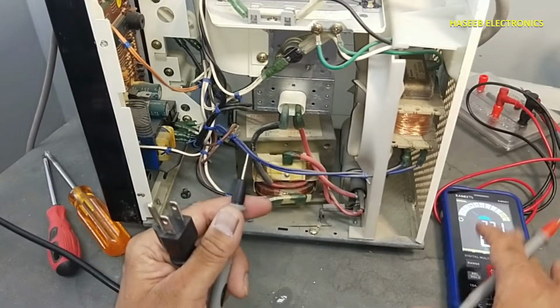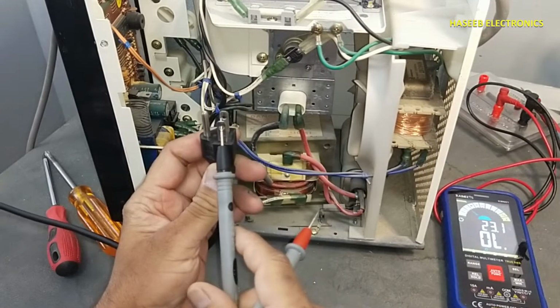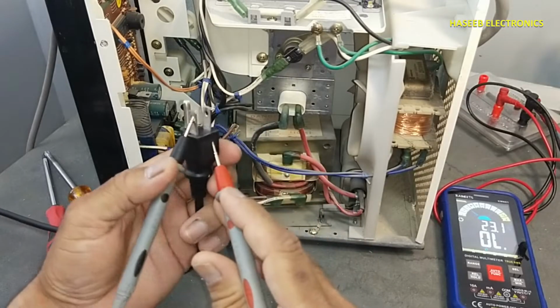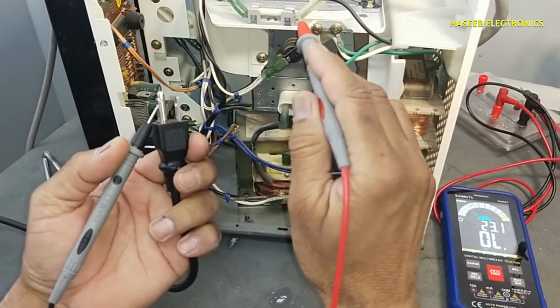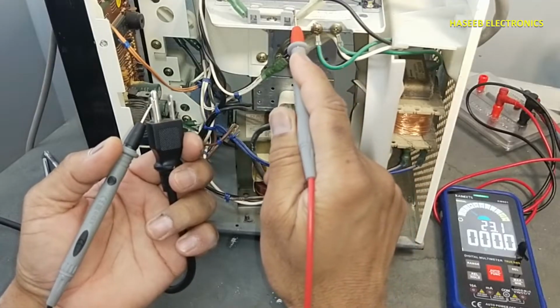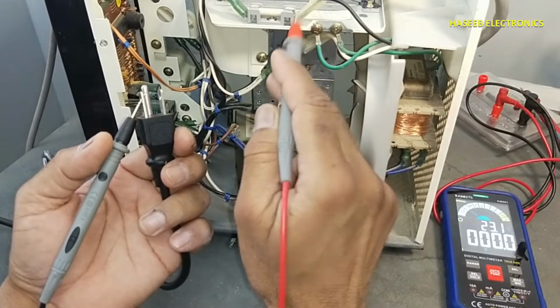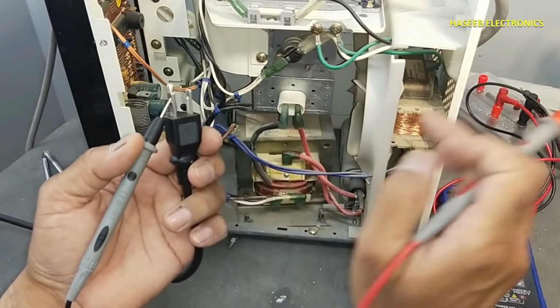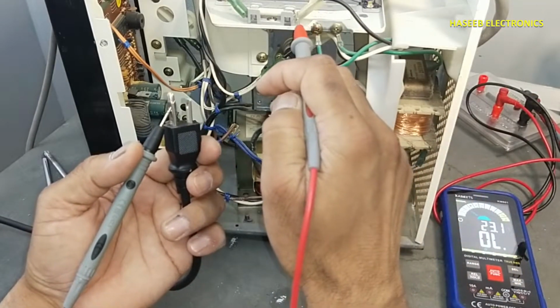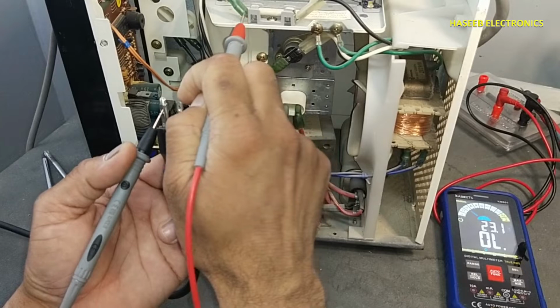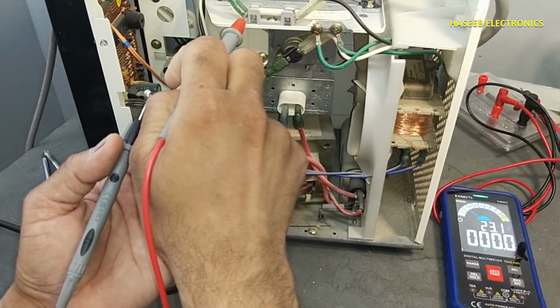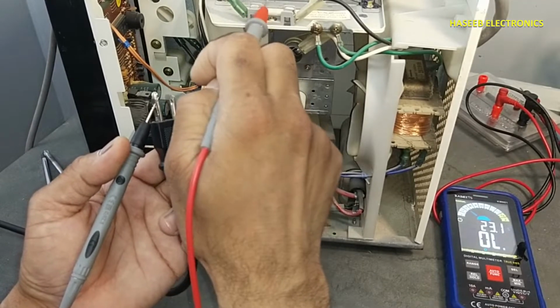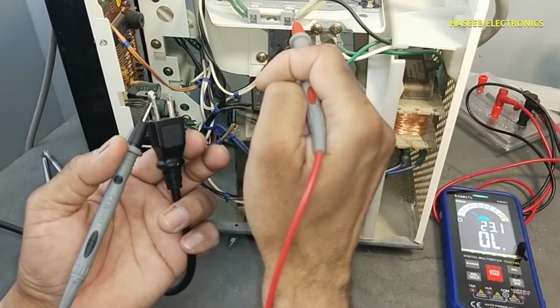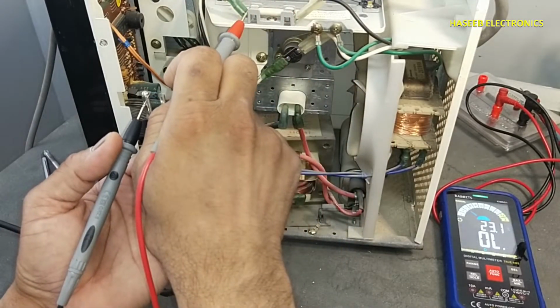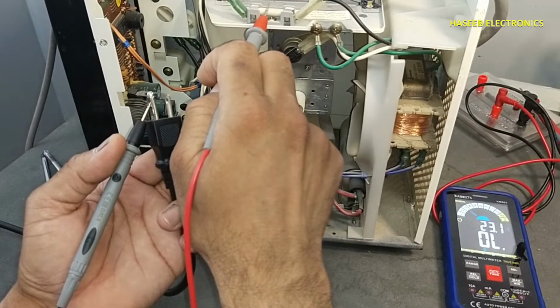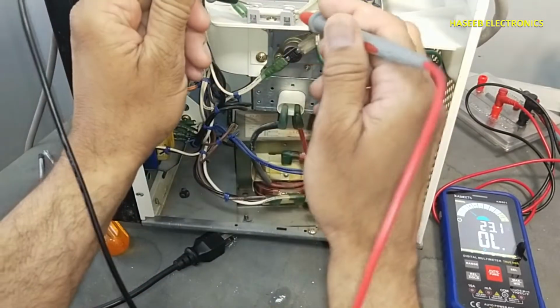Set the multimeter to continuity. Connect one lead to one input terminal, and connect the other to one end of the fuse. If it is giving continuity here, that means from this point to this point the cable is good. Now check the second side. If it is giving continuity, that means this fuse is good. If it gives continuity here but not here, the fuse is open. We can also verify the fuse in this way.